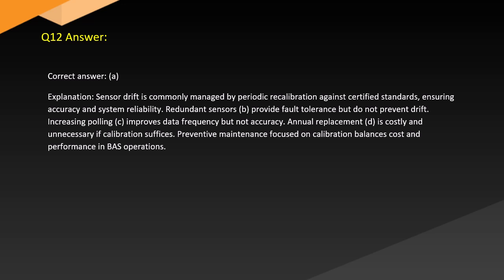Answer. Correct answer: A. Explanation. Sensor drift is commonly managed by periodic recalibration against certified standards, ensuring accuracy and system reliability. Redundant sensors, B, provide fault tolerance but do not prevent drift. Increasing polling, C, improves data frequency but not accuracy. Annual replacement, D, is costly and unnecessary if calibration suffices. Preventive maintenance focused on calibration balances cost and performance in BAS operations.